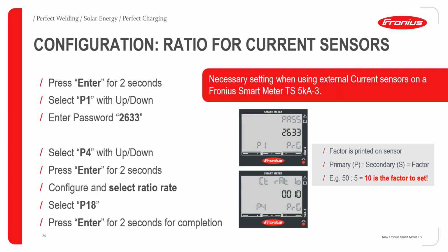And another piece of information about configuring the inverter and smart meter display is that you have to set up the ratio of the current sensors. Remember, I mentioned that for the 5K3 smart meter, you have to use external current sensors. Then after calculating the ratio, for example, if the primary and secondary, then you can decide the factor. If it is 50 on primary and 5 on secondary, then the factor is 10. You just simply divide it. If it is 100 on the primary side and 5 on secondary side, then the factor will be 20, things like that.